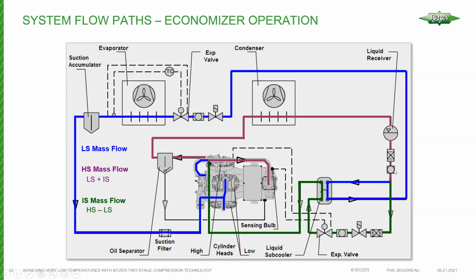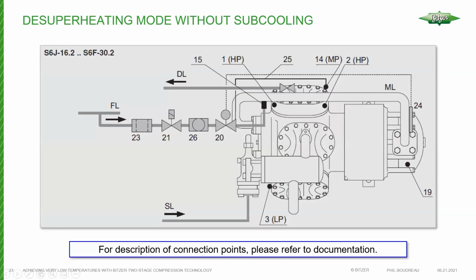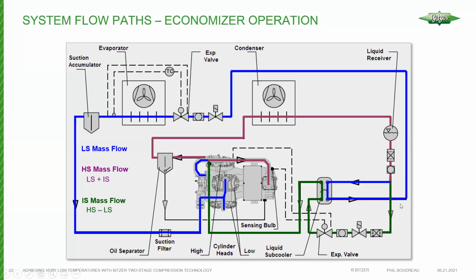So going back to the receiver outlet on the far right of this drawing, you can see where that line split off. So we followed the blue line, which is your liquid, okay, traveling to the main evaporator. We're refrigerating that. But in order to accomplish this, we need to take some of the refrigerant from the liquid line, which is generally going to be piped off the bottom of the liquid line. So we have a good quality liquid there. Keep in mind, this is auxiliary cooling for the compressor as well. First and foremost, it's about interstage cooling. But secondly, as a nice side benefit, we're subcooling to improve capacity and efficiency as well.